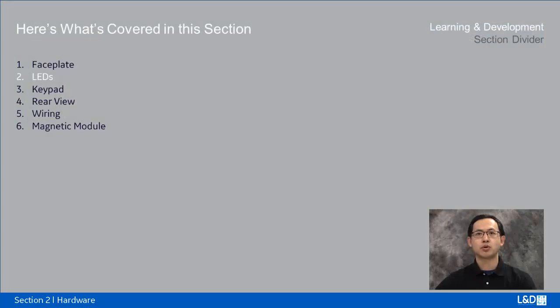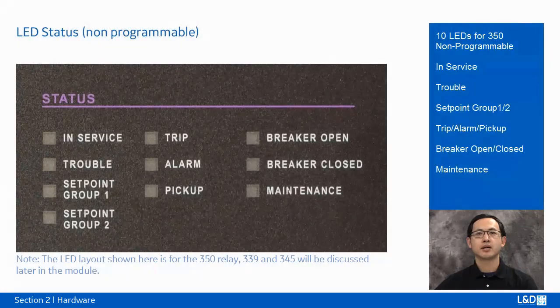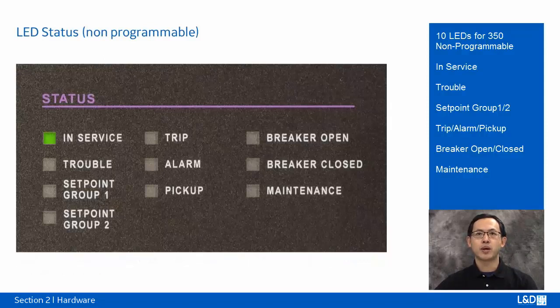Next, we'll talk about more details of the LEDs. In this training module, we'll only talk about the LEDs of the 350 feeder relay. For the 339 motor relay and 345 transformer relay, we will introduce their own LEDs in their specific modules. The In Service LED will turn on green when the relay is set to ready in the setup menu and no major self-test error has been detected. The Trouble LED will turn on orange when the relay is not programmed or upon detecting a major self-test error.